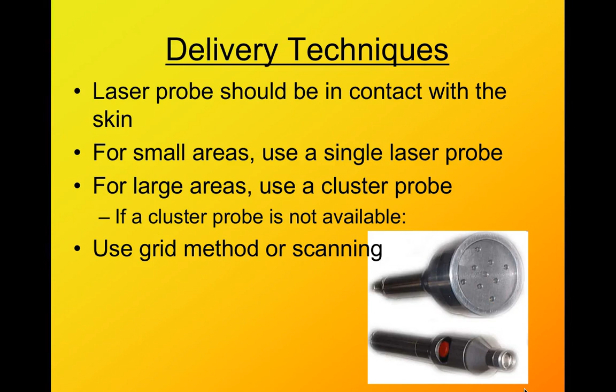That's really important as well, that the dosage is really based on that treatment time, how much light we expose during that time. If you're doing a larger area than just the area of your diode, your treatment time has to increase for each time you are moving that device. For example, with trigger points, slowly moving the laser probe, maybe getting a little bit of pressure down, a little massaging effect, could be beneficial as well. But again, you have to know how big your area is so that you increase the time that you need.